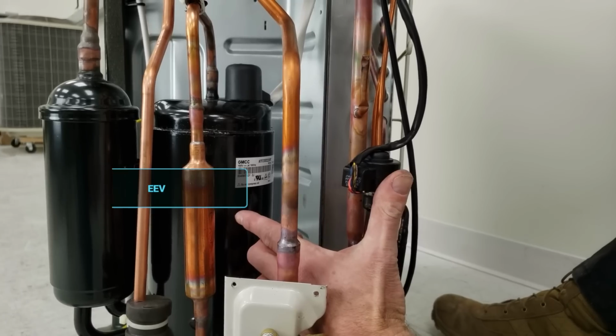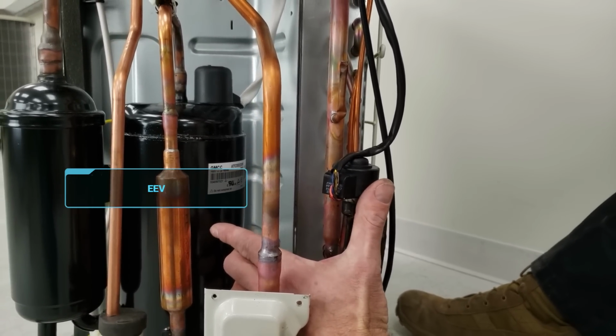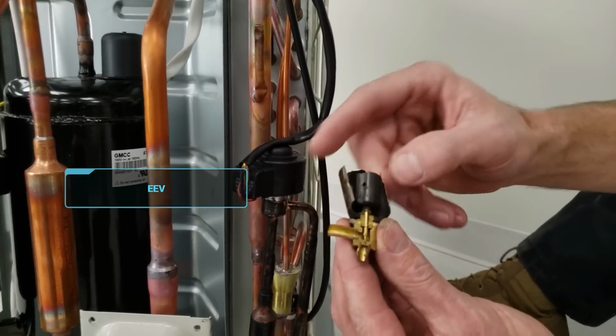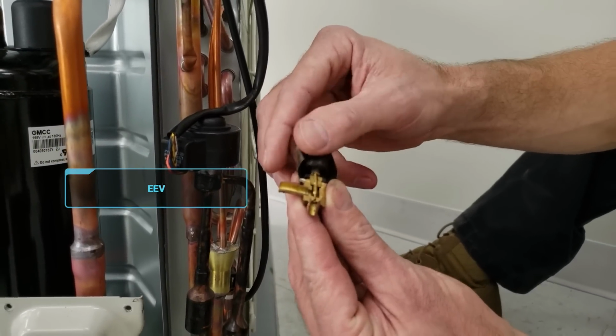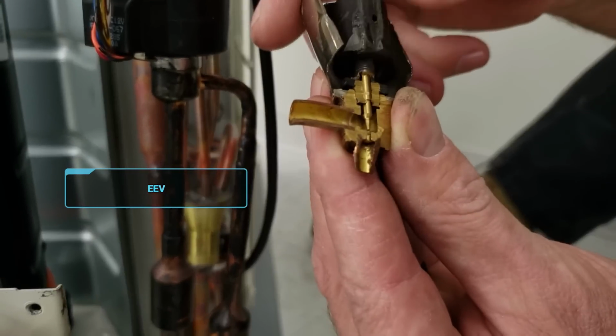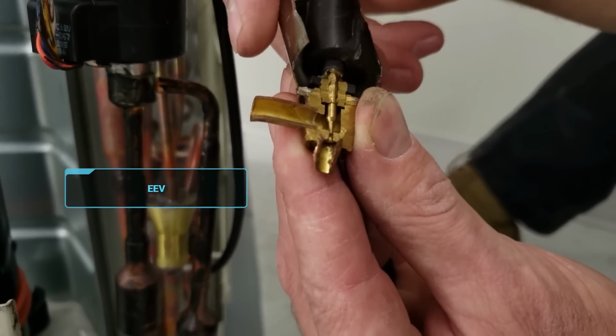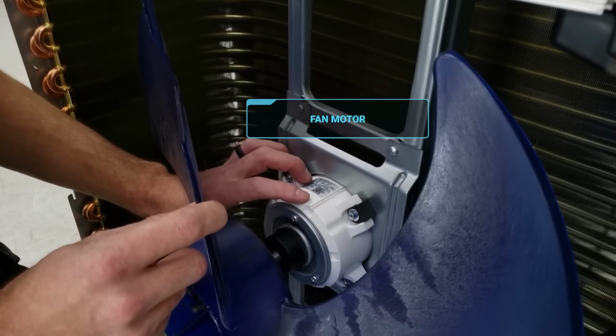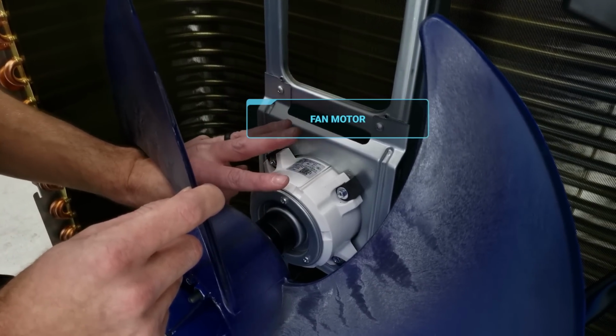And what's funny is that with some mini-splits, you can technically get away with calling it an inverter even if you have, say, a capillary tube as a metering device. You're either going to have a capillary tube or an EEV, and the term inverter is really talking about the compressor drive. But the high efficiency inverter systems are going to have your inverter-driven compressor. You're going to have an EEV, electric expansion valve metering device, in the outdoor unit, and then you'll have a fan motor in the outdoor unit as well. It's most likely inverter-driven, and at the indoor unit, you're going to have either a speed control board inside the fan motor or outside the fan motor, and some of those are also inverter-driven as well.